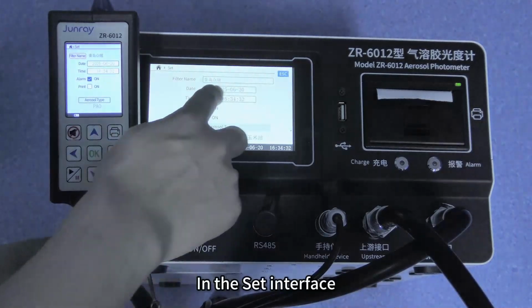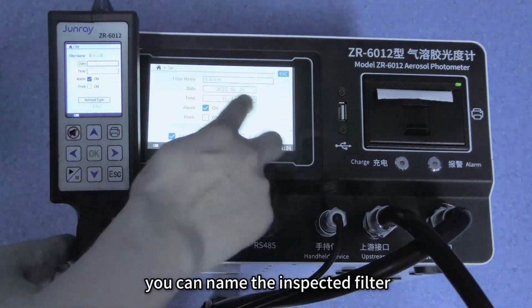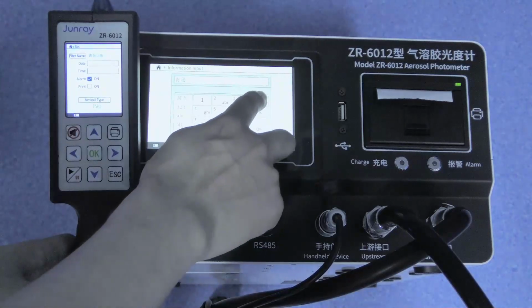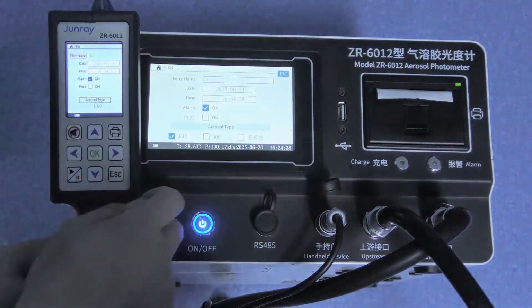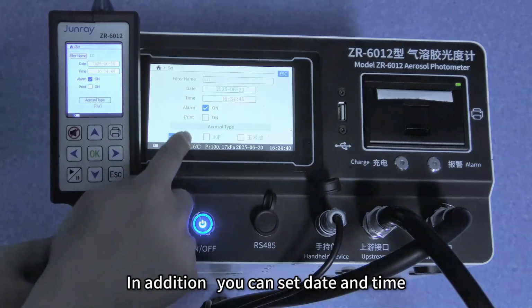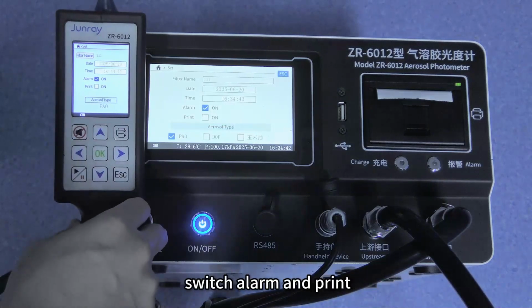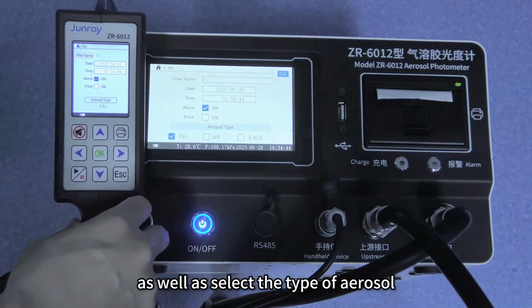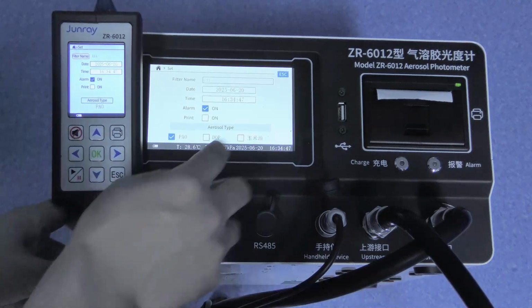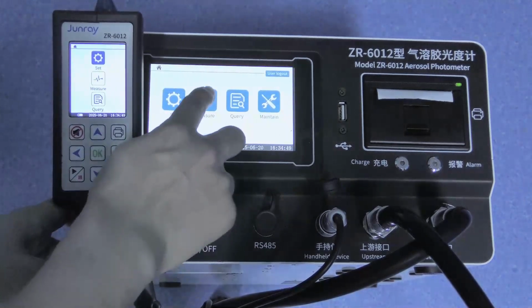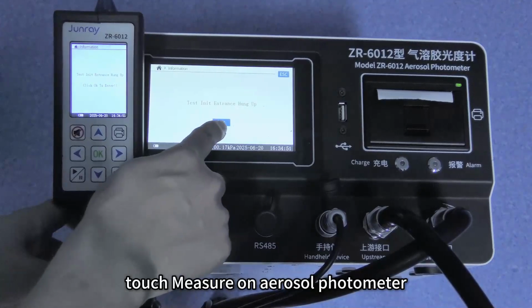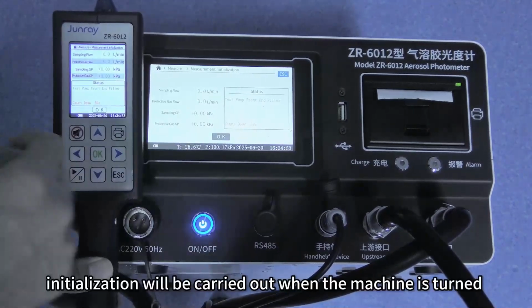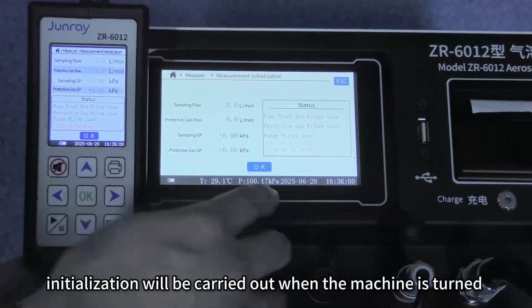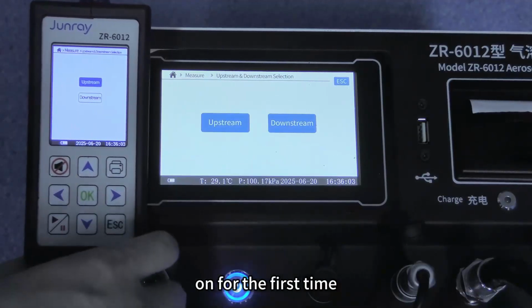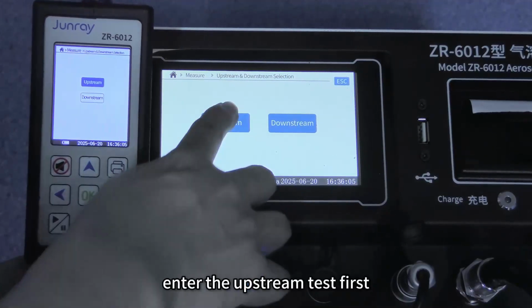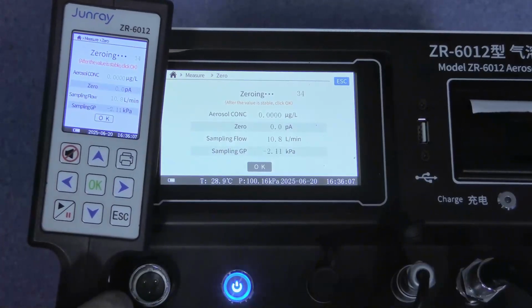In the set interface, you can name the inspected filter. In addition, you can set date and time, switch alarm and print, as well as select the type of aerosol. After setting, touch measure on aerosol photometer, then touch OK. Initialization will be carried out when the machine is turned on for the first time. After that, enter the upstream test first.